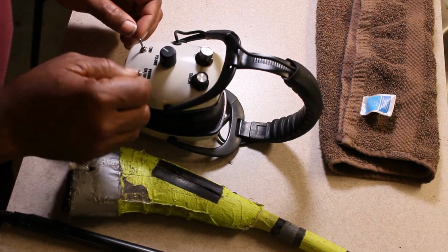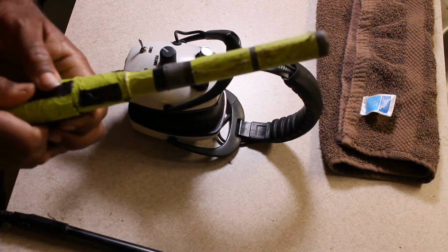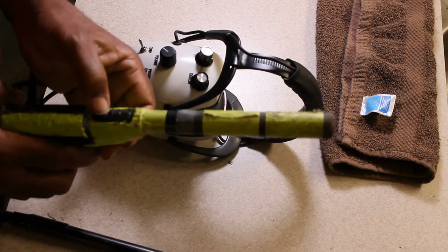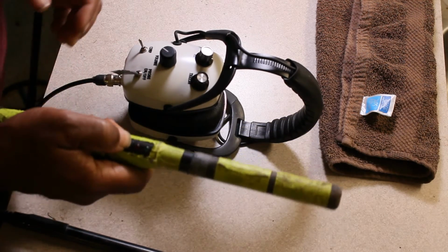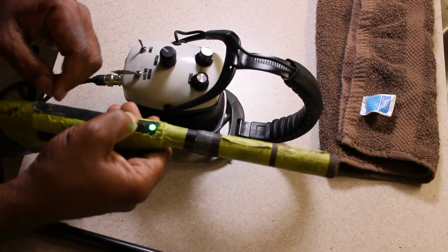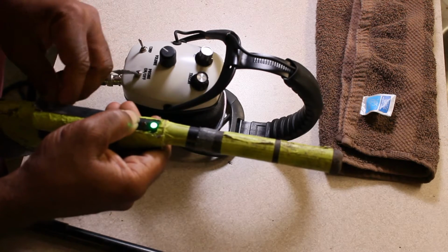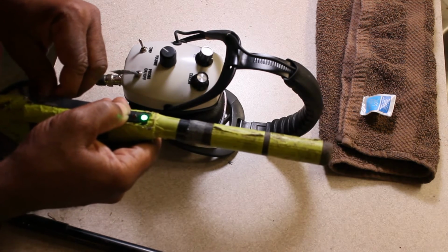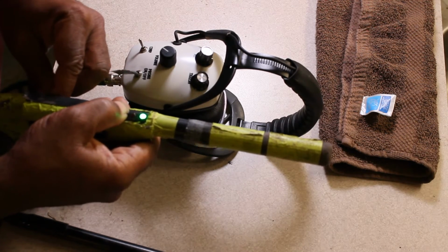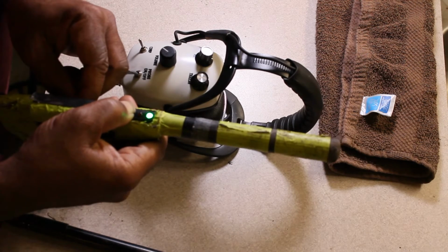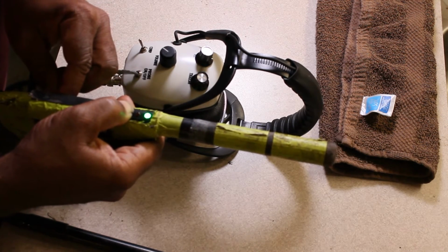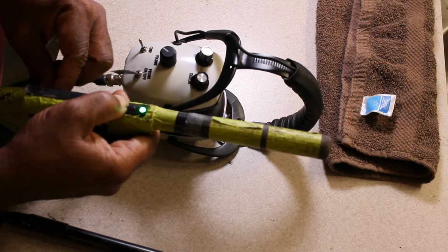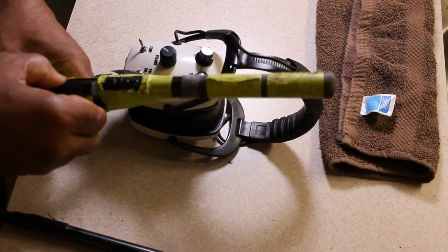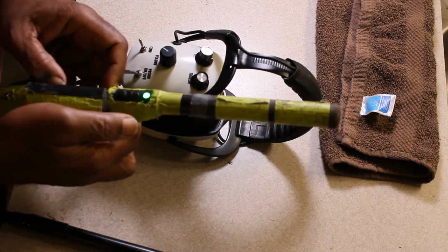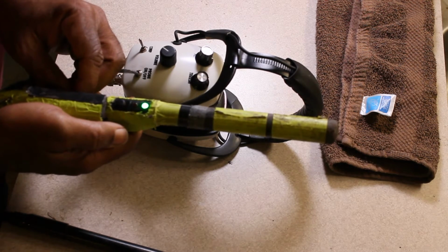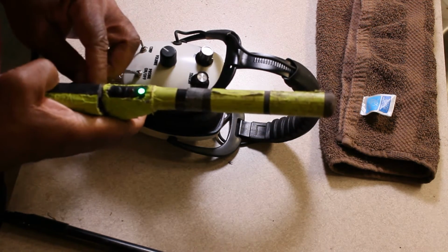But with this, you have to set frequency and threshold. I'm going to set it on this because I really can't give you a good auditory sound on the Uniprobe because it is headphones. So basically, see, you've got this sound. So I can up or change the threshold. I could change the frequency in case there's interference. And that also would require I change the threshold. So I can make the threshold loud and then reduce it a bit till it's just a whisper. And the best way to actually do that is to turn it on full time and then set the threshold down and then turn it back where the button controls it.